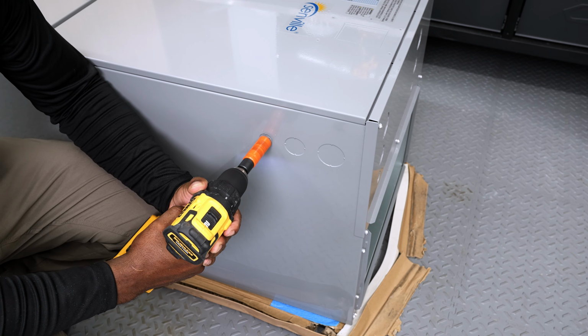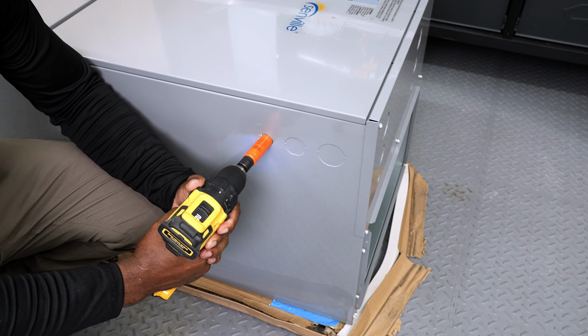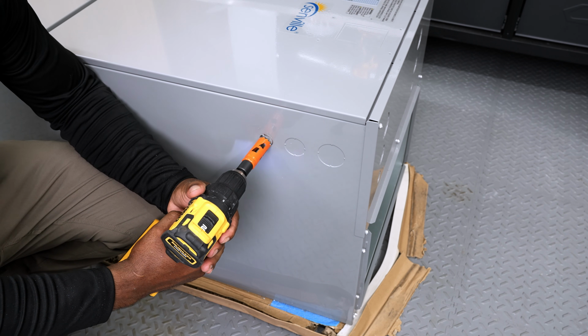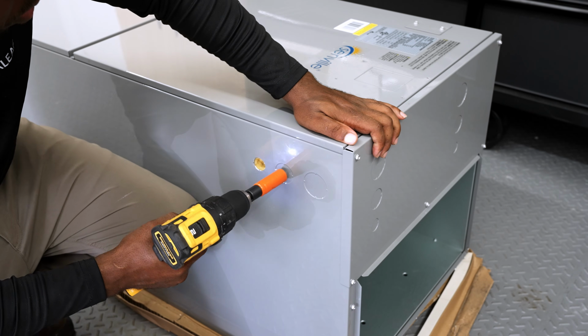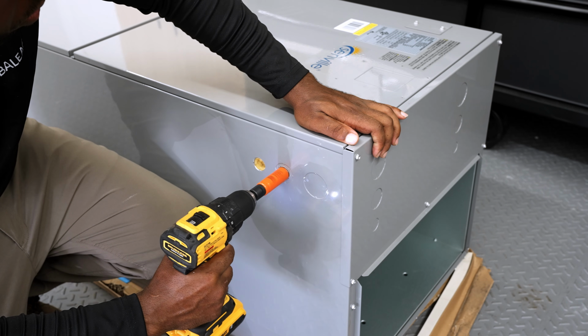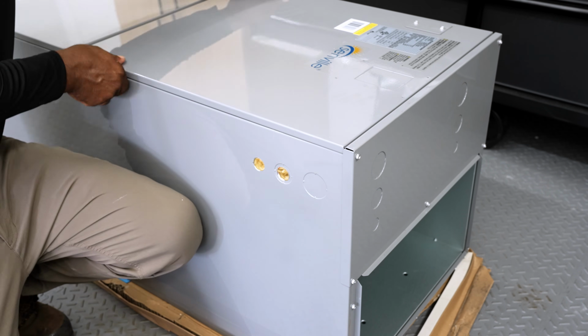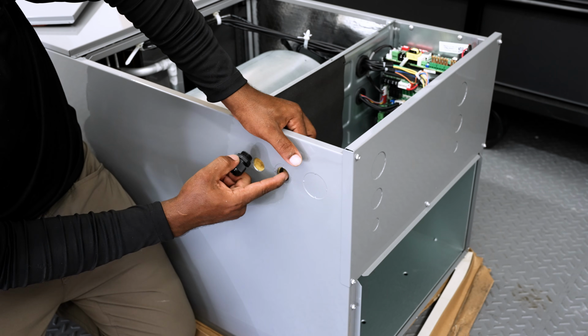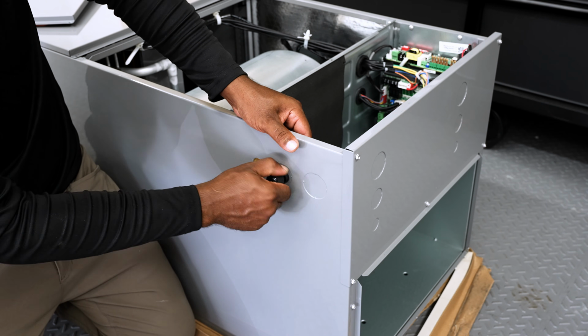I'm going to use a 3/4 inch hole saw to cut my own holes. I'm going to make 2 holes, one for the high voltage wire going to the electrical panel, and one for the low voltage wires for the thermostat, the communication cable, and the water flow switch. Anytime you're passing wire through metal, you should always sleeve it.